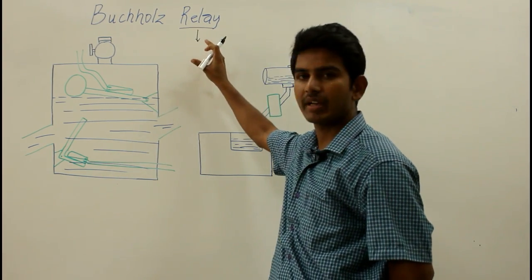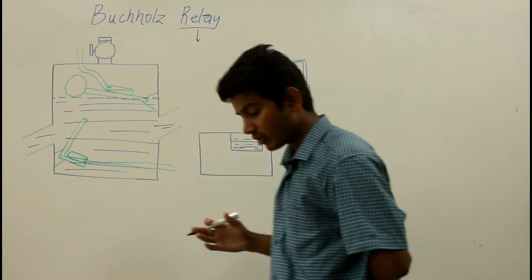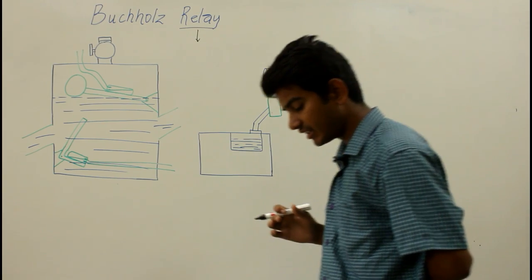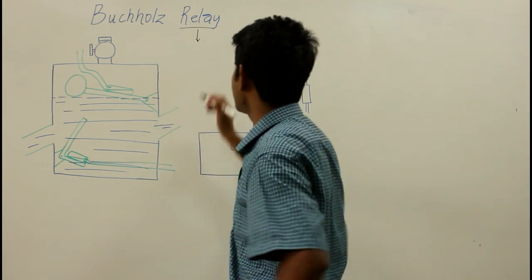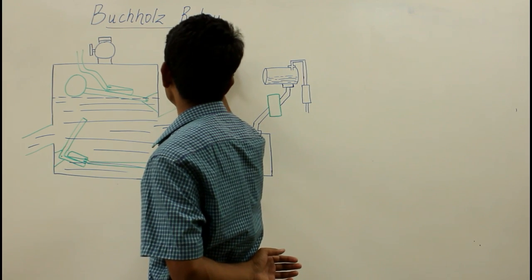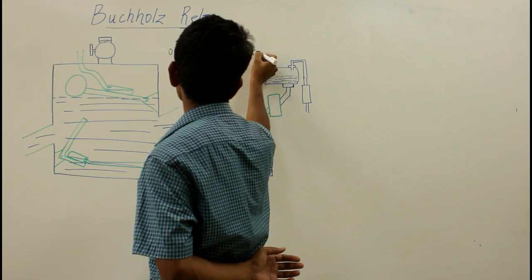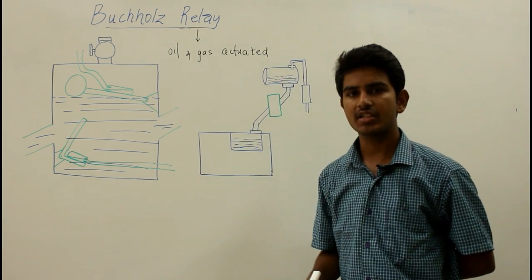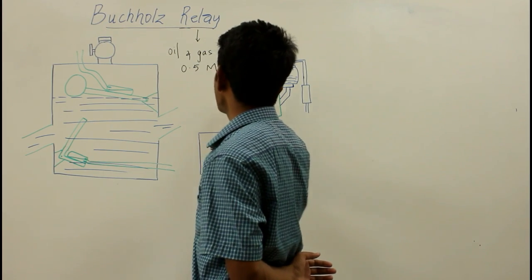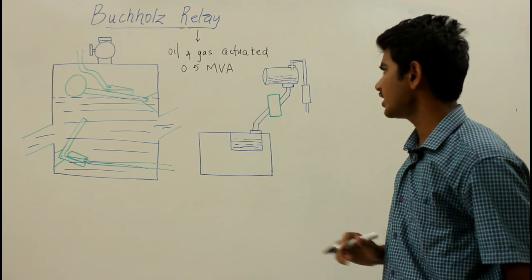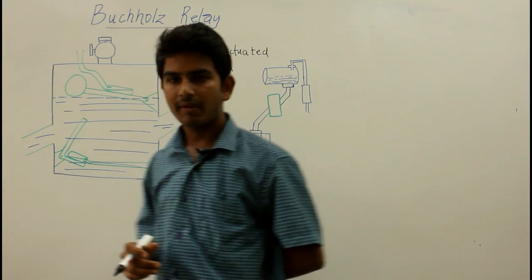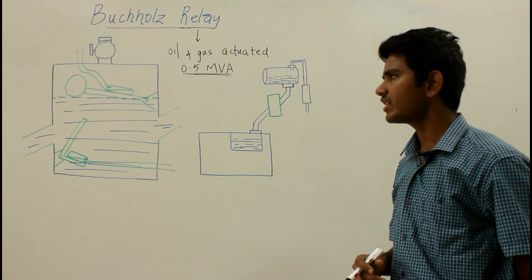Relays can be electromagnetic relays, solid state relays, reed relays, thermal relays, or hybrid relays. The Buchholz relay is a type of oil and gas actuated protective relay which is universally employed on all oil-immersed transformers having a rating more than 0.5 MVA. The Buchholz relay is not provided for transformers with a rating below 0.5 MVA because of economical considerations.